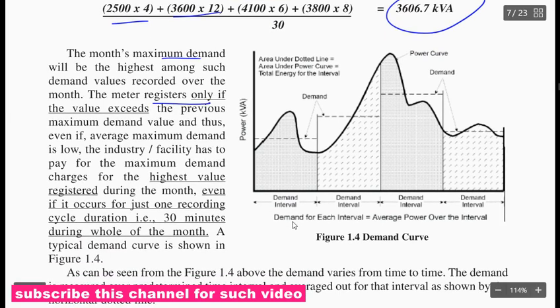The meter registers only if the value exceeds the previous maximum demand value, and thus even if the average maximum demand is low, the industry facility has to pay the maximum demand charge for the highest value registered during the month, even if it occurs for just one recording cycle, that is 30 minutes, during the whole of the month.